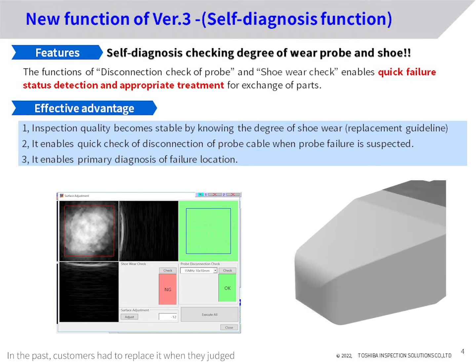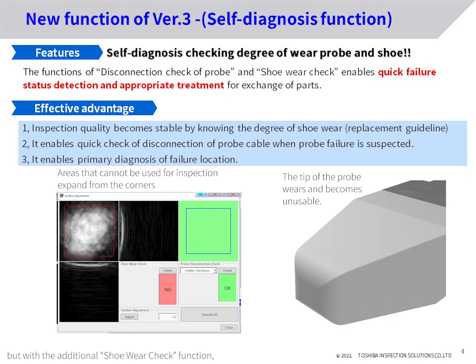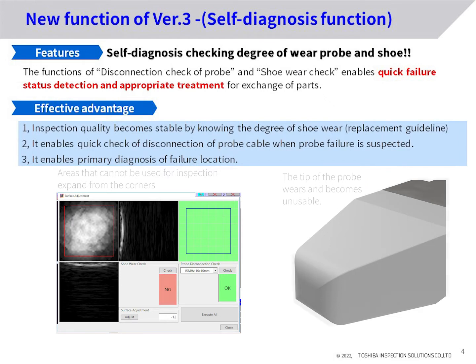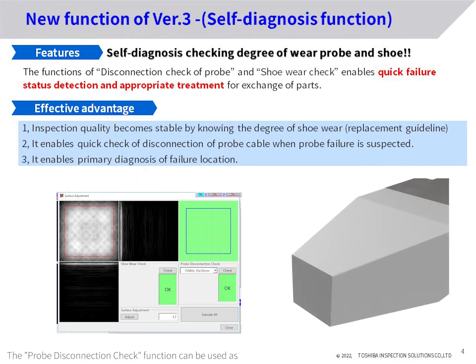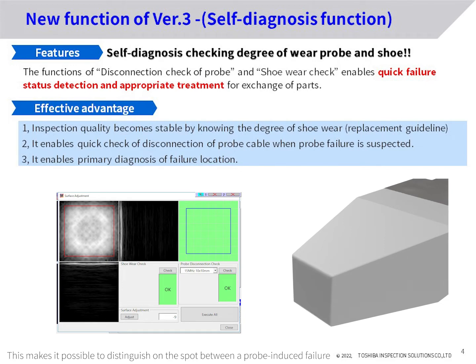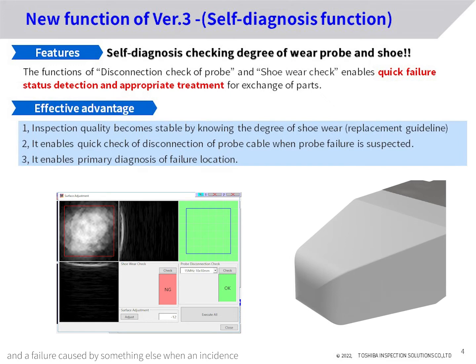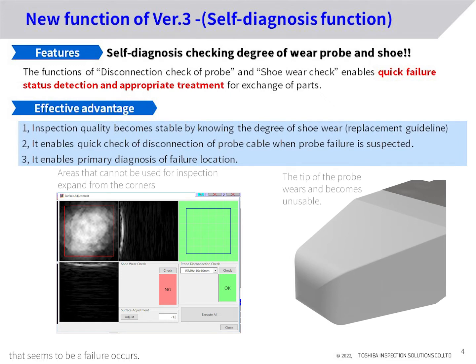In the past, customers had to replace the shoe when they judged that accuracy had deteriorated, but with the additional shoe wear check function, it is now possible to objectively know when to replace it. The probe disconnection check function can be used as the initial diagnosis when an incident that seems to be a failure occurs. This makes it possible to distinguish on the spot between a probe-induced failure and a failure caused by something else.